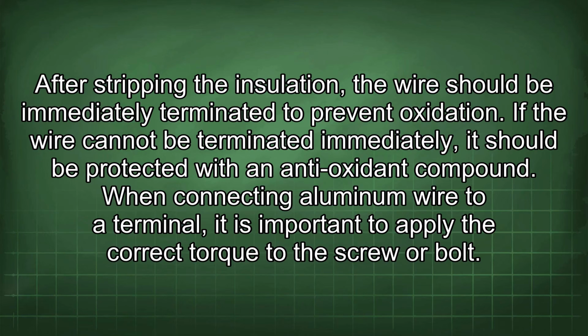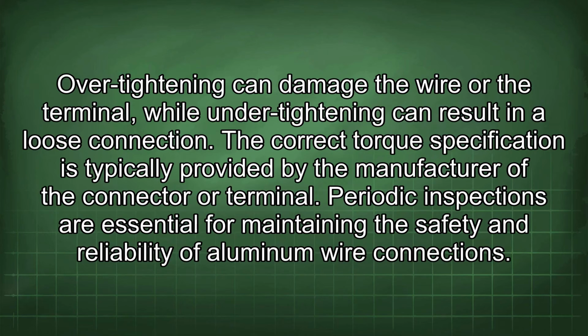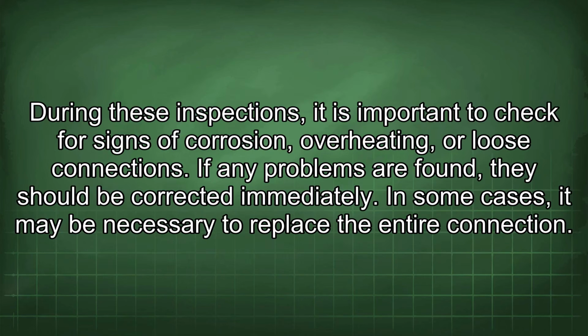When connecting aluminum wire to a terminal, it is important to apply the correct torque to the screw or bolt. Over-tightening can damage the wire or the terminal, while under-tightening can result in a loose connection. The correct torque specification is typically provided by the manufacturer of the connector or terminal. Periodic inspections are essential for maintaining the safety and reliability of aluminum wire connections. During these inspections, it is important to check for signs of corrosion, overheating, or loose connections.